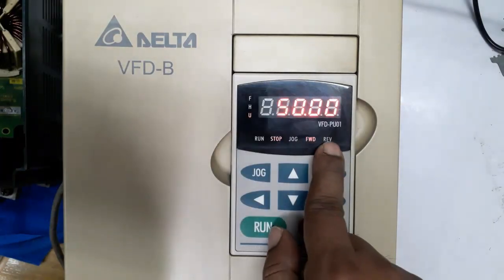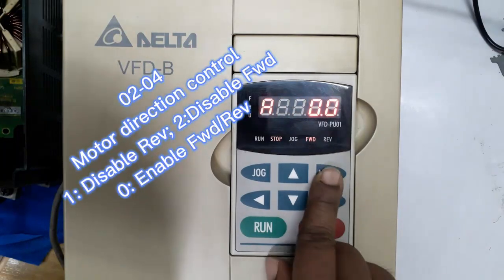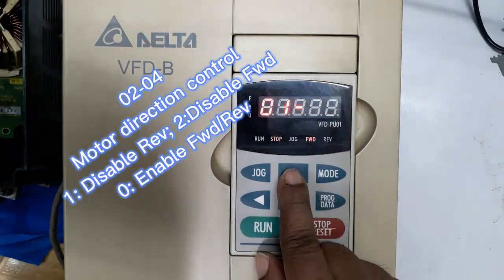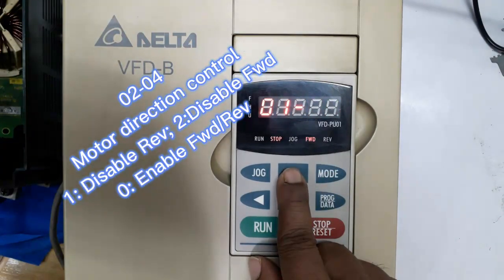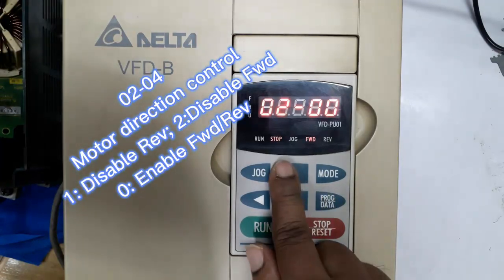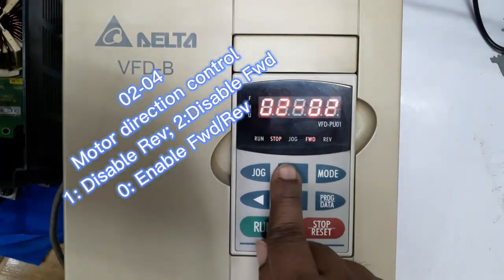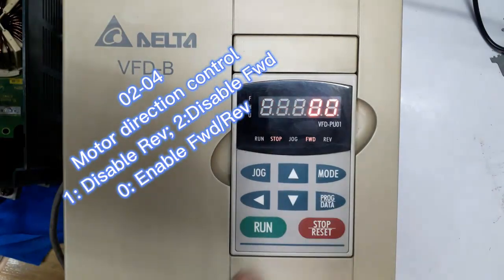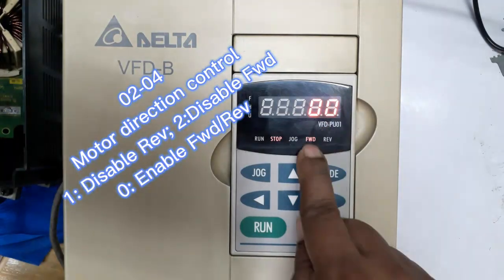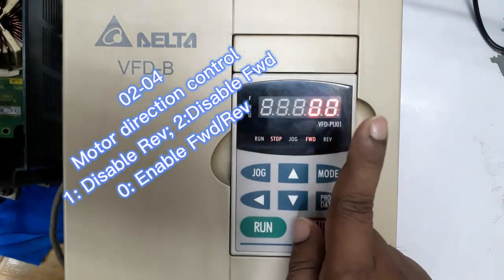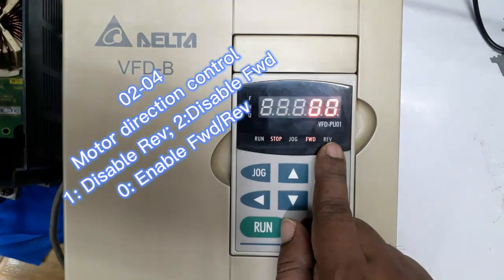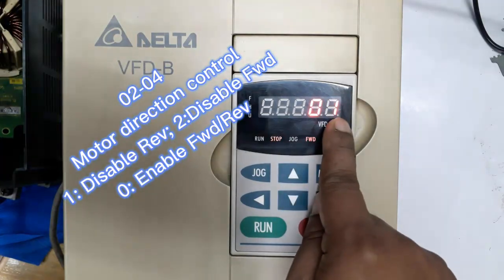Motor direction control parameter. Parameter group 2 and parameter 04, that means 2-04 is the parameter for motor direction control, where the default setting is 0, that means both forward and reverse operation are allowed.